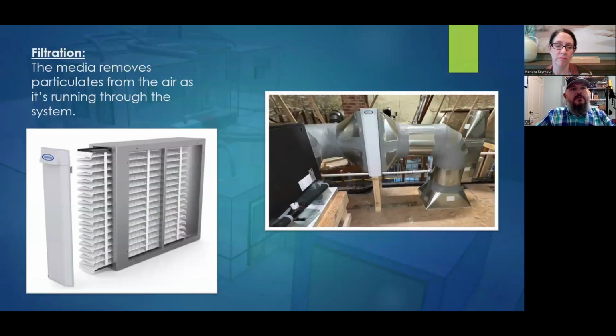So filtration, effective filtration is essential for maintaining good indoor air quality. This particular setup is my preferred setup. The filter cabinet can get designed and integrated into the system close to the indoor unit. The whole system must be designed for good filtration. And this is more difficult than it seems, believe it or not. So this is the filter cabinet here. It's close to the unit. This is my unit here. So if there's any leakage or anything on this side of the system, it gets filtered and goes through that. All of my filters are MERV 16.